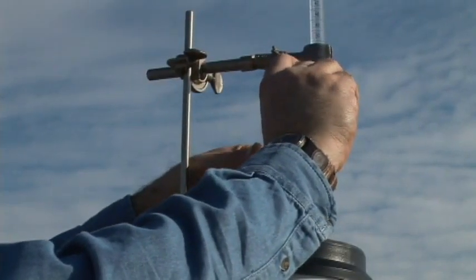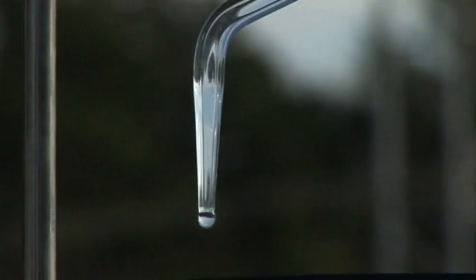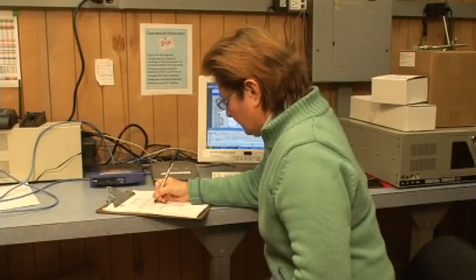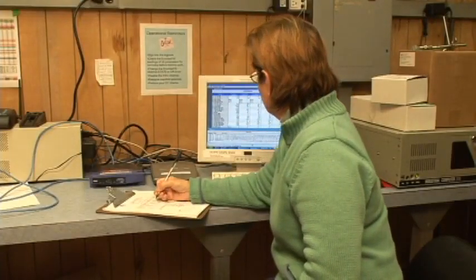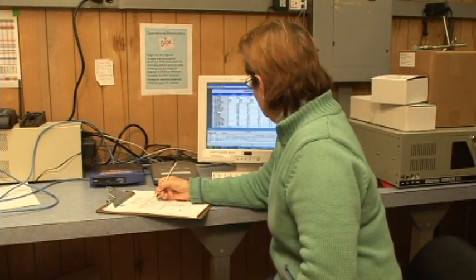It is now time to communicate with the inside technician and let them know that the calibration will now start. The outside technician will now turn the stopcock so that the water begins to drip into the funnel. The dripping should be set to allow 7 to 10 drips per minute. After a number of drips, you should hear the tipping bucket tip. This will be an audible click that you will hear. This constitutes one tip, which should correspond to a certain amount of rainfall. At this time, communicate with the inside technician and let them know that one of the tips has commenced. The DAS should now record the rainfall.